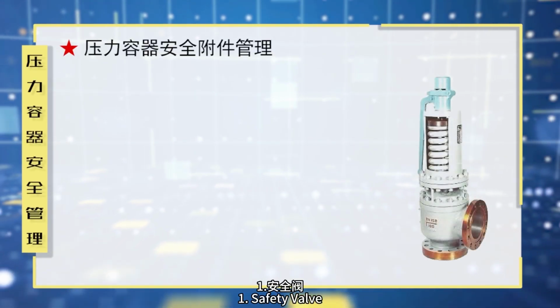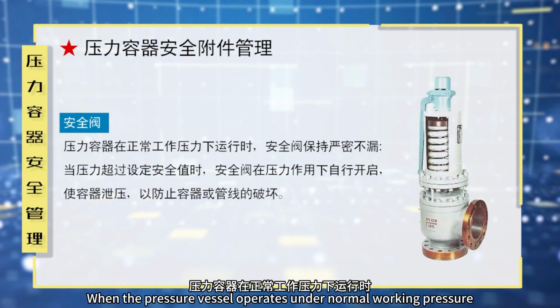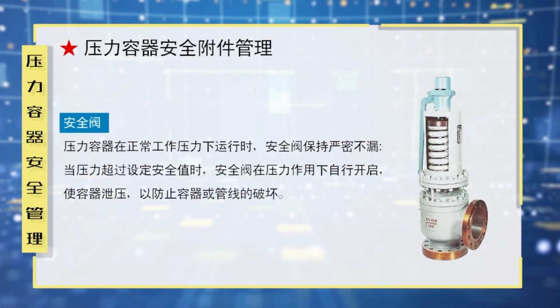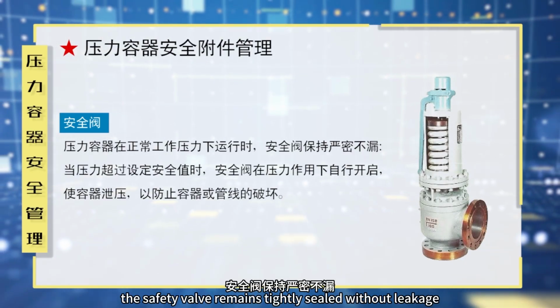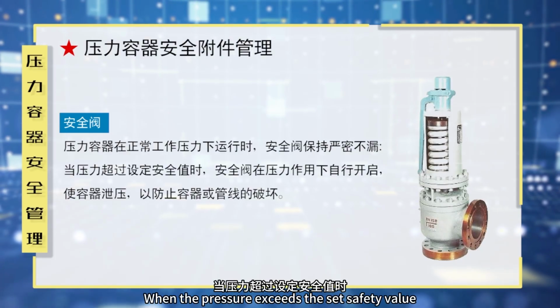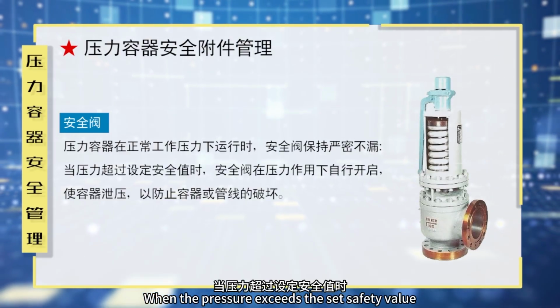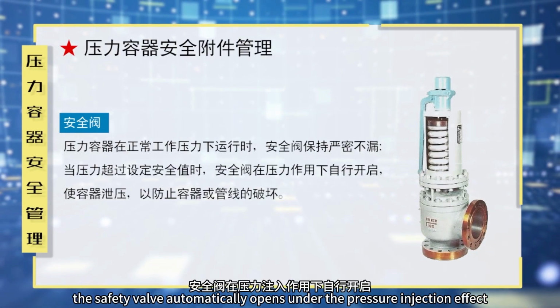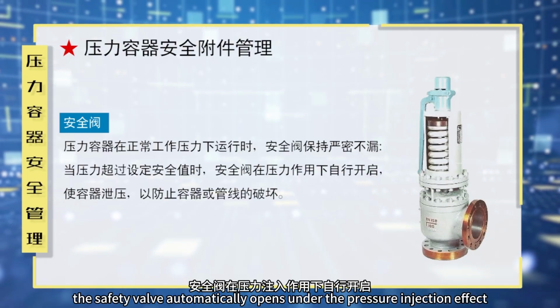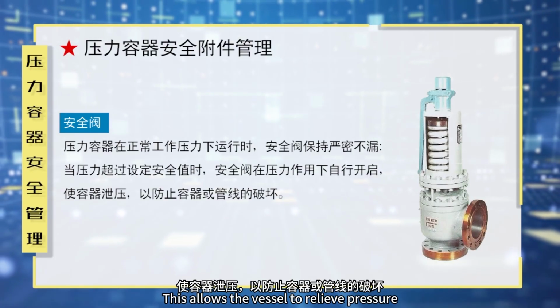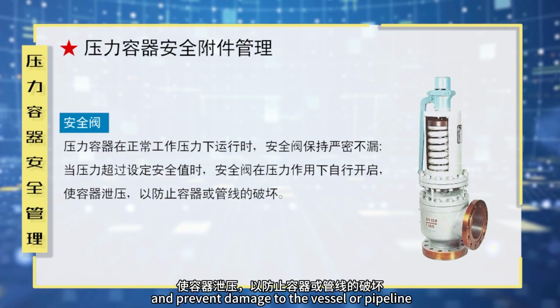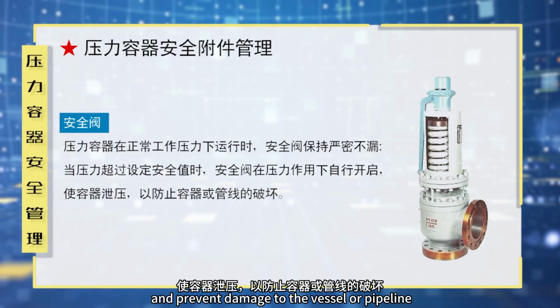First, safety valve. When the pressure vessel operates under normal working pressure, the safety valve remains tightly sealed without leakage. When the pressure exceeds the set safety value, the safety valve automatically opens under the pressure injection effect. This allows the vessel to relieve pressure and prevent damage to the vessel or pipeline.